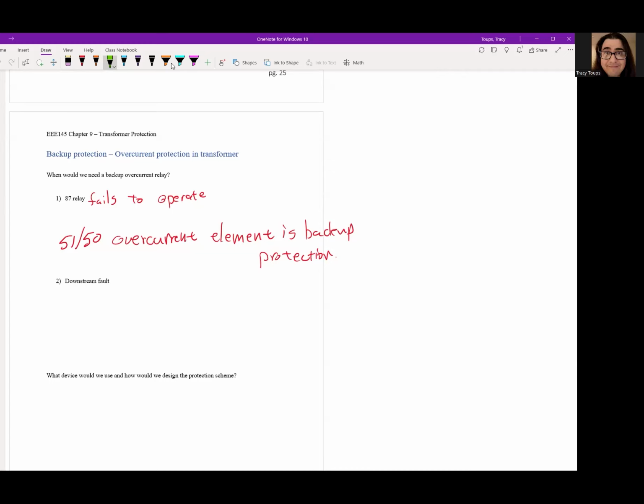Now, another reason why we need a backup relay, even if the 87 differential will work: what about downstream faults on the feeders? So this is like if a feeder protection fails, right? Remember, we like to have backups of backups. So what backs up a feeder protection? Remember, a feeder is a low voltage circuit breaker downstream of the transformer. If that fails, the upstream device is the actual transformer itself, right? So let me say that again.